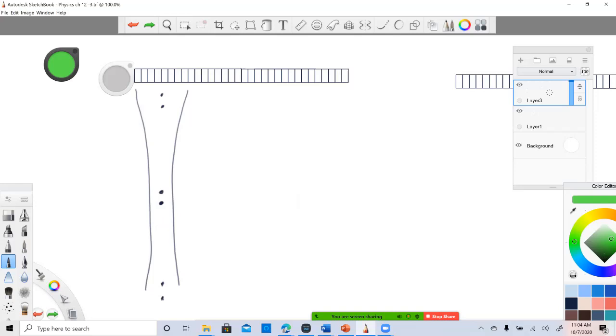If two dots are both inside the beam, remember that's one pulse creating an echo that is from the same exact depth. It's going to have a smeared out echo. We're not going to be able to see it as two. So that's poor lateral resolution.